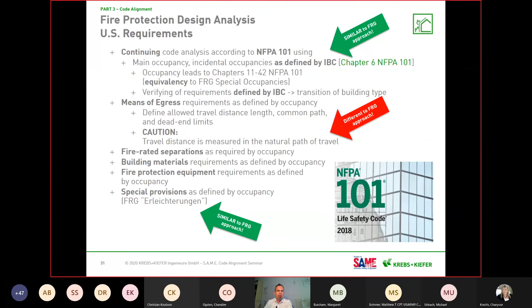The means of egress: some of you might think that 35 meters of travel distance to exit is the most stringent requirement always, ever. And it's not actually. The most stringent requirement most of the time is the common path length that is defined by the US codes, because that is a part that we apparently do not know in Germany. We don't measure common path length, but I think that's a very critical and very good way to think about means of egress and make the path to exit more safe.